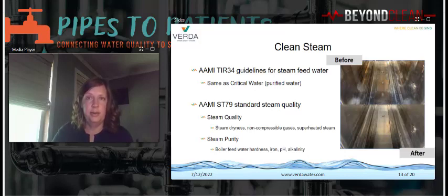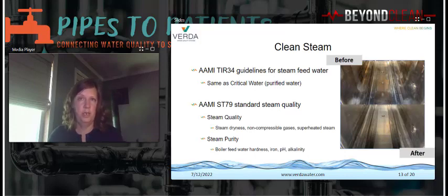Today's modern high-rated boilers are more sensitive to the quality of the steam feed water, and more steam sterilizers on the market now operate off purified feed water or clean steam. And with sterile reprocessing steam only accounting for less than 5% of the total steam production for the average medical center facility, it may make sense to produce clean, dry steam for sterile reprocessing separate from facility steam.